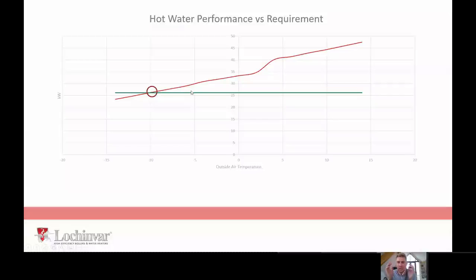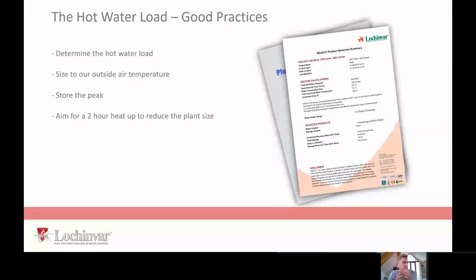Okay, so when we're looking at air source heat pumps for hot water, it's quite an interesting one, really, because of how the industry originally worked. There might be some people a bit more senior in here, but a long time ago, the industry had a long period of time, and you've probably seen it. You've probably seen summer boilers, you know, this sort of thing. And basically, what you had in plant rooms was a load of 3,000 litre calorifiers storing the peak of hot water, and they'd all have long heat up times on.